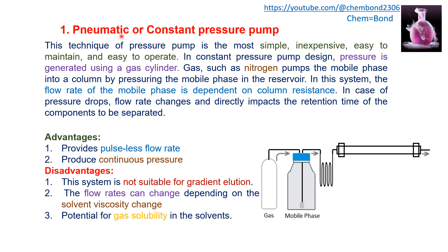The first type is the pneumatic or constant pressure pump. This is the most simple, inexpensive, and easy to operate pump design. Pressure is generated using a gas cylinder; gas such as nitrogen pumps the mobile phase into the column by pressurizing the mobile phase from the solvent reservoir. In this system, the flow rate of the mobile phase is dependent on column system resistance. In case of pressure drops, the flow rate changes and directly impacts the retention time of the component to be separated.